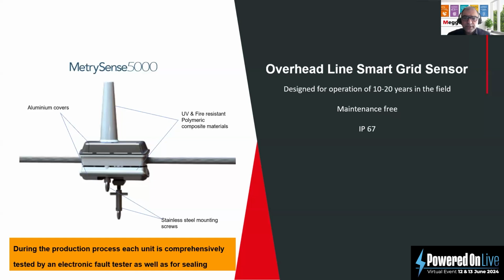It's designed for operation of up to 20 years in the network, maintenance free, with IP67. The material is a UV and fire resistant polymeric composite material, with aluminum covers, and it includes two stainless steel parts. The main one is for the conductor, and the secondary is for the sensor itself. Each sensor is tested in the factory by an electronic fault tester, as well as for sealing.